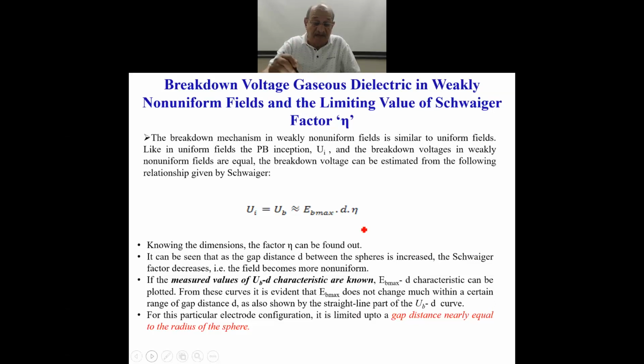be estimated with the help of this formula if you know the Schweiger factor eta correctly. And here you can always calculate eta if you know the dimensions of the electrode, because eta is nothing but equal to E mean by E max in the electrode configuration. And it can be seen that the gap distance d between the sphere, or between any two plates, we'll come to the between two spheres, it has been calculated. As it is increased, the Schweiger factor decreases. When you increase the gap distance between the two electrodes, the Schweiger factor decreases. The field becomes more non-uniform.